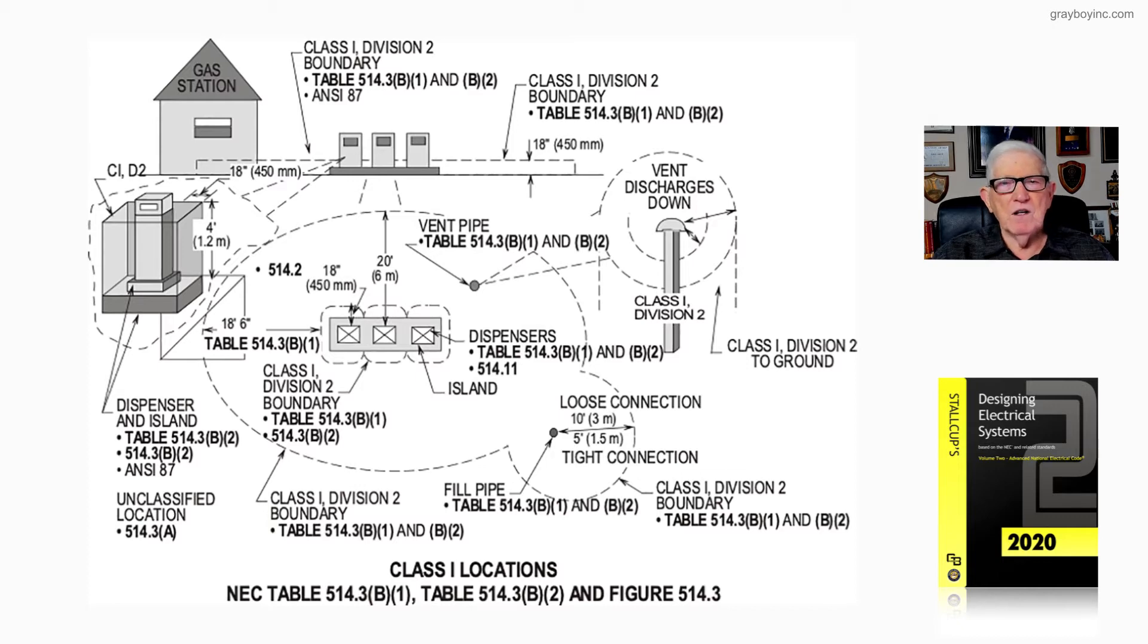Notice sometimes you have those dispenser pumps closer to a filling station, a little store inside, a fast grocery type. Then sometimes you'll come around the building, and then the door will be to the left of that 18 inch boundary so that you don't have to classify inside. And there's a solid wall on the wall facing the dispensers.